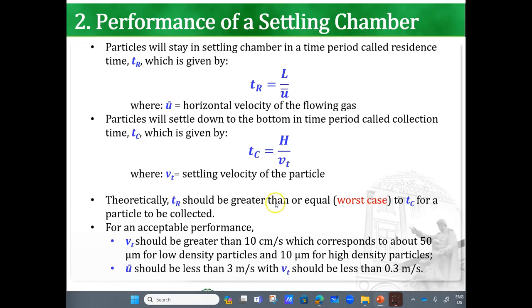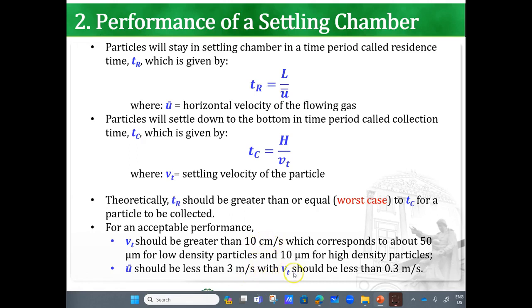Theoretically, t_r should be greater than or equal to t_c; otherwise, you won't expect any collection — the residence time in the chamber should be bigger than the collection time. For acceptable performance, v_t should be greater than 10 centimeters per second, corresponding to about 50 microns for low-density particles and 10 microns for high-density particles. The horizontal velocity u-bar should be less than 3 meters per second, with v_t less than 0.3 meters per second.